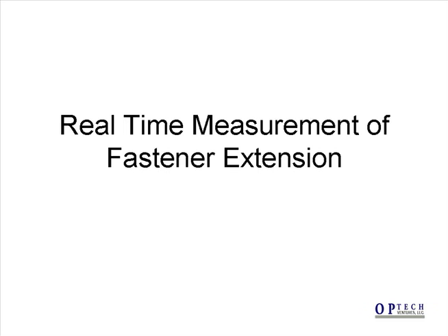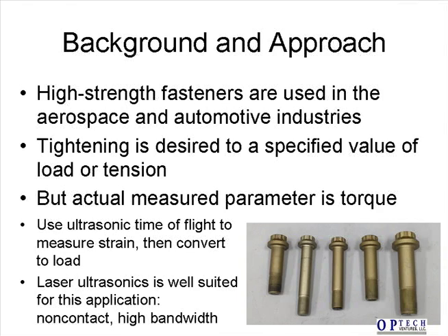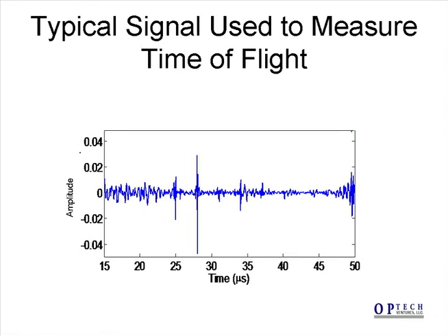The final application is real-time measurement of fastener extension. The photo shows a selection of fasteners used for aircraft assembly. Each fastener has a specified value of load or tension during tightening of the nut, but only torque can be measured during tightening, which can be influenced by friction. However, ultrasonic time of flight can be used to measure the strain during tightening, which can then be converted to stress or load. The temporal signals represent waves that travel to the opposite end of the fastener and return, and can readily be used to measure the change in time of flight that results from loading the fastener.